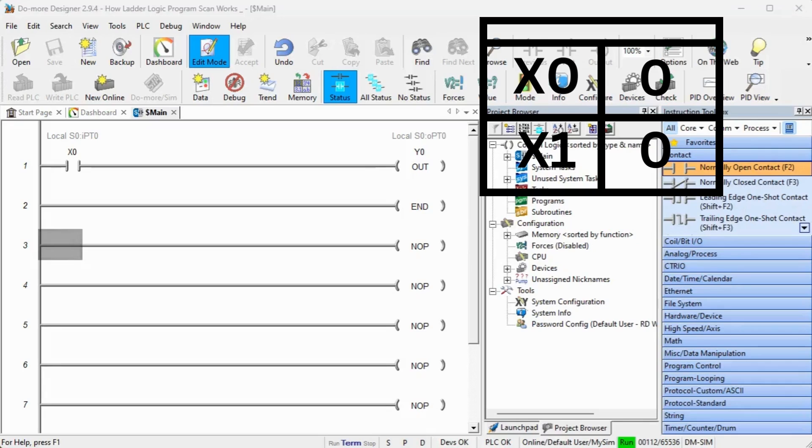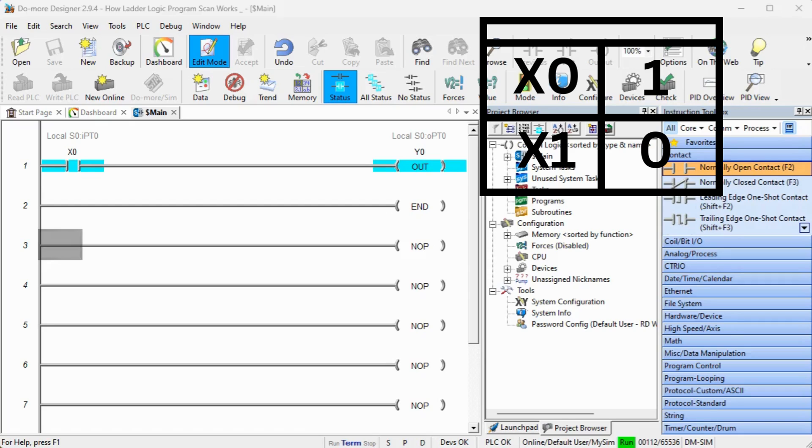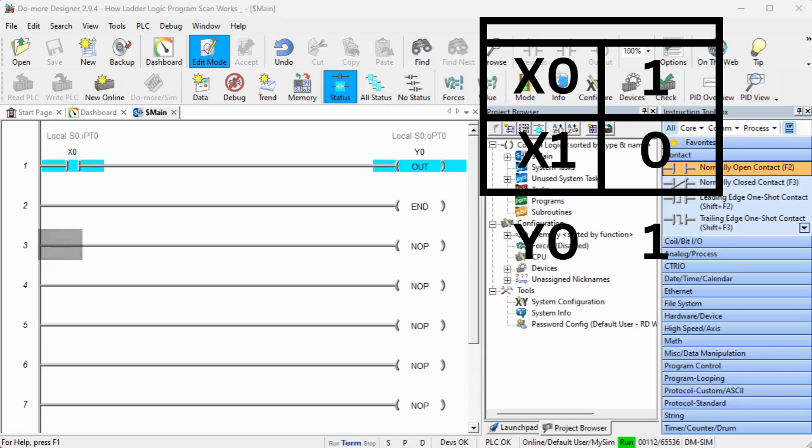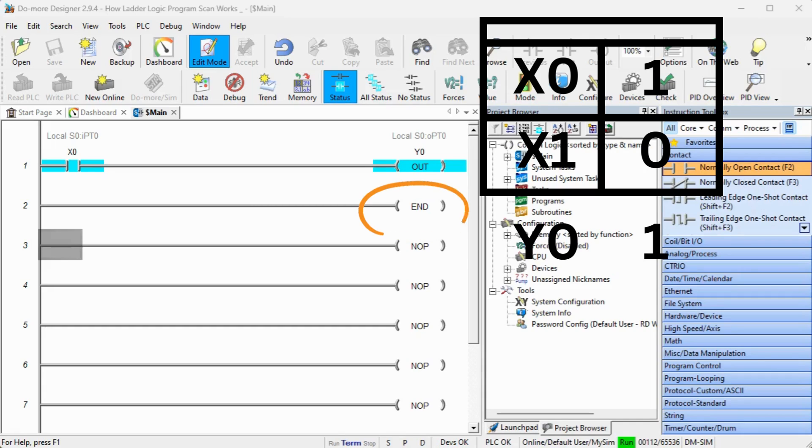This sample program has two rungs. When x0 is turned on, the scan will read the inputs and update the memory table. It will then execute the program. The first rung will look at the content for x0 in the memory table. Since this is on, it will now look at the output and turn this output on in the memory table. The second rung is the end statement. When the scan sees this, it will stop the execution of the program and move to the next part of the scan. Remember that the scan happens several times per second.